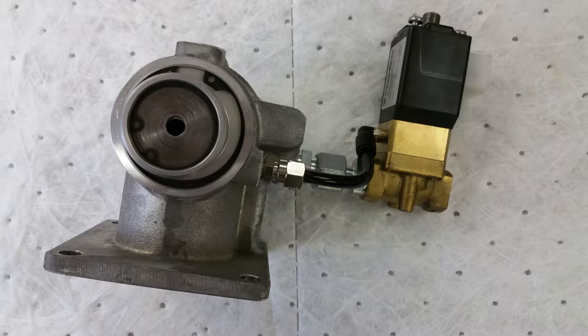Prior to beginning work, make sure the sump pressure is at 0 psi before shutting off power to the compressor and locking out the machine. Instructions on how to check sump pressure can be found below in the description of this video.